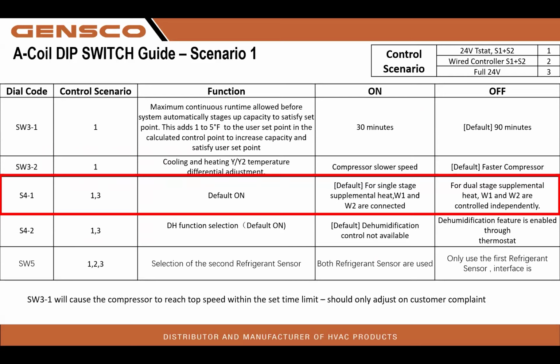SW4-1, control scenario 1 and 3. Default is on. Default is for single stage supplemental heat. W1 and W2 are connected. And for dual stage supplemental heat, W1 and W2 are controlled independently. That would be in the off position.